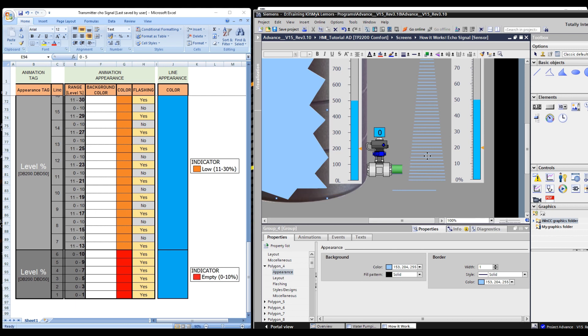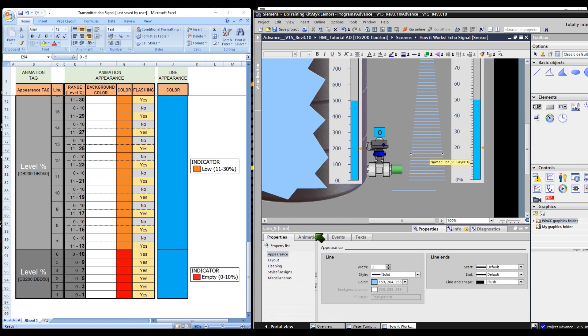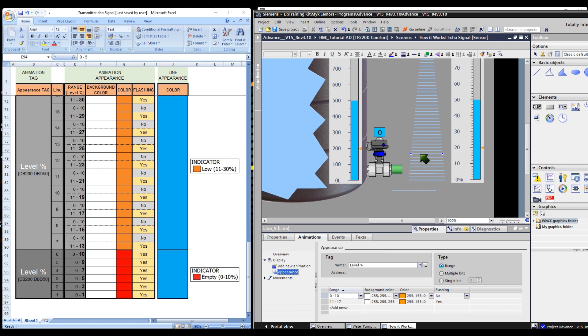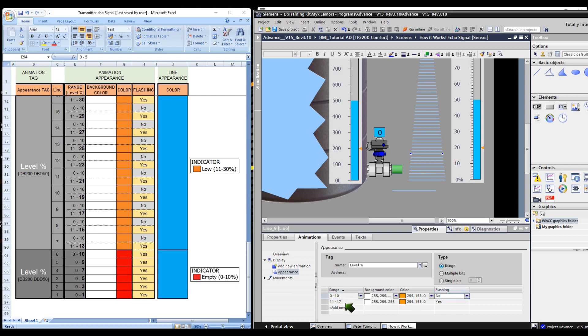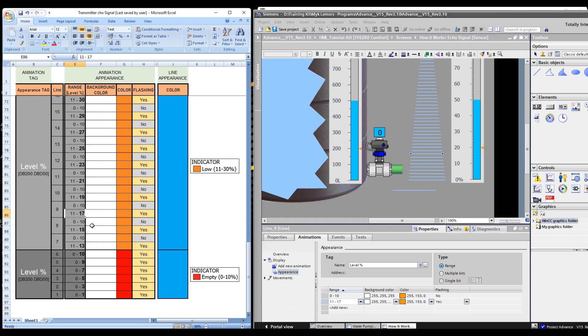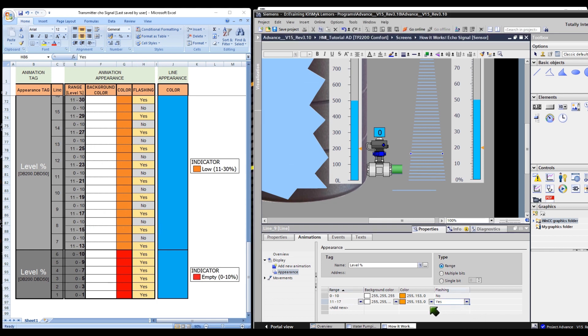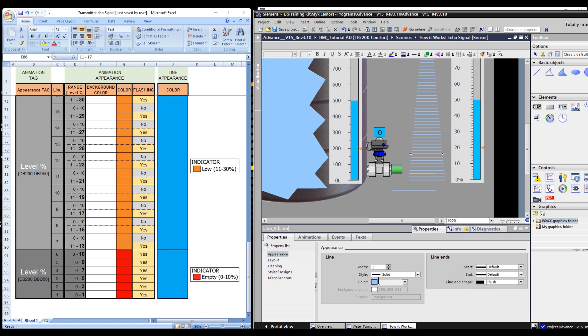Let's choose another line object. Each line object can be set with more ranges or multiple ranges. The first range means the animation appears when the level is 0 to 10% — orange is the color of this object line within this range, and flashing is disabled. The next range means the animation appears when the level is 11 to 17%, and flashing is enabled. The color flashes orange and white. Outside this range, the object line will appear sky blue, matching the color of the water.